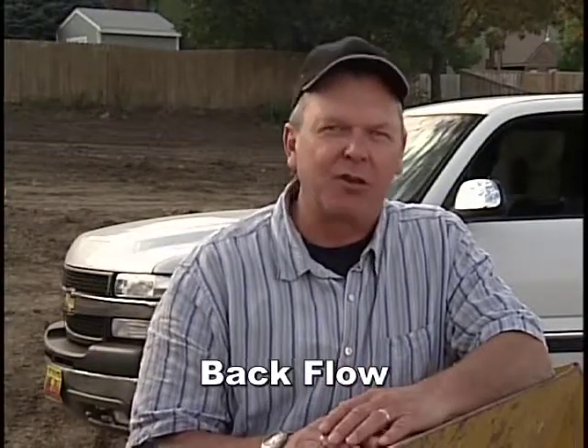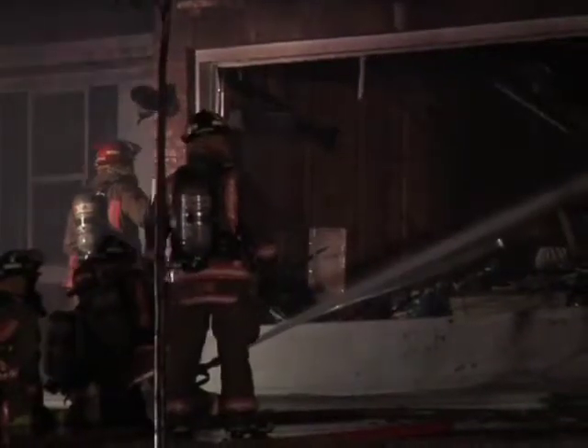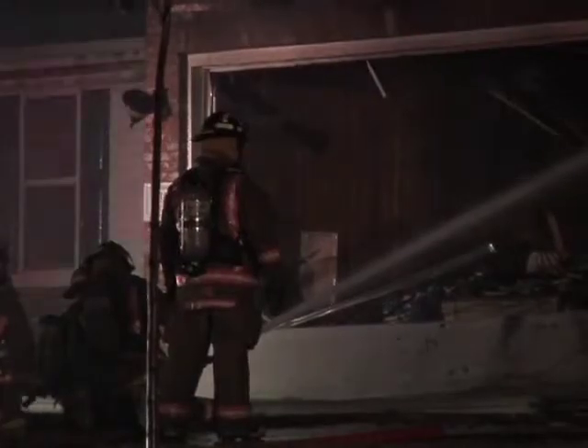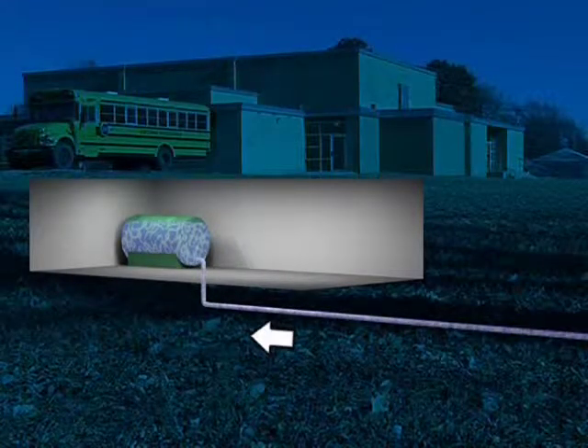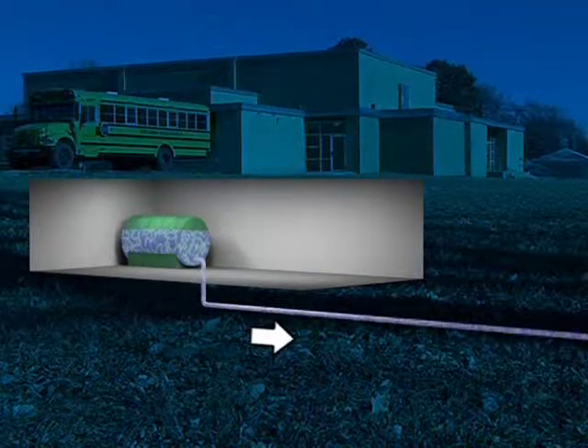Now, backflow is the reversal of the flow of water from its normal or intended direction of flow. Let's use animation to show how all of this works. In your water system, backflow can easily be caused by a break in one of the water lines or by the fire department turning on a fire hydrant to fight a fire. When that backflow happens, a cross-connection that isn't controlled will allow the bad water to flow back into the good water in your water system. Here you see the water that's going to the school start to flow backwards. If there is an uncontrolled cross-connection on the school's boiler, then the boiler water will flow back into the water system. The way to stop backflow is with a program you set up to control the cross-connections. If the cross-connection doesn't allow the backflow, then your drinking water stays potable.